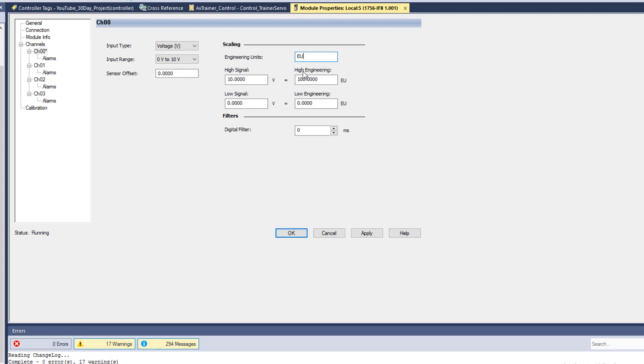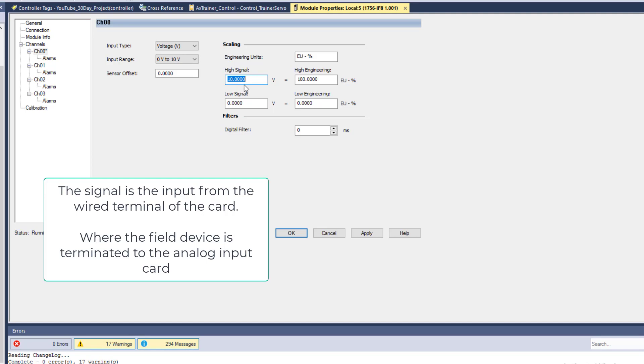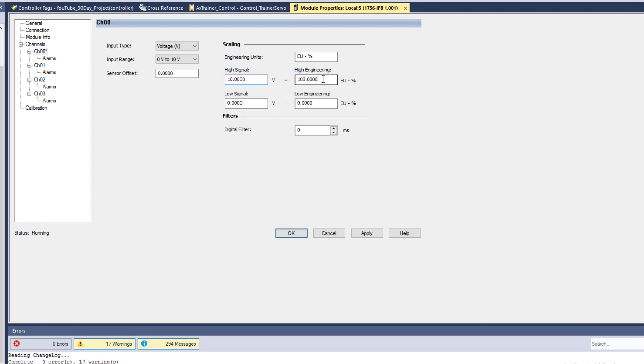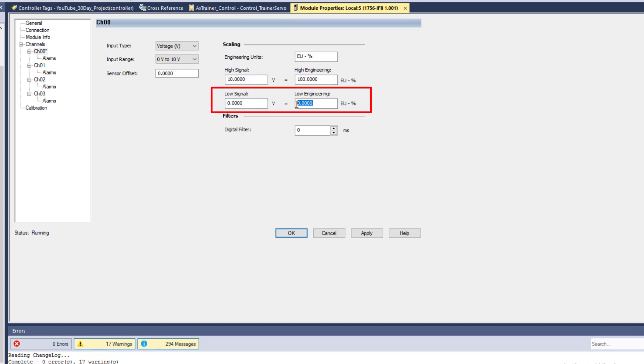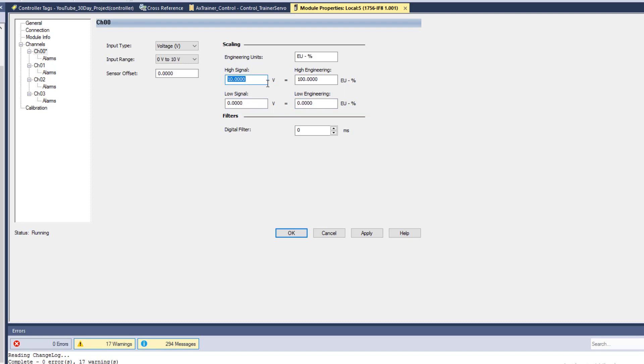In your engineering units — this is just a name field — I'm going to put 'percentage' so you can see that populate. The high signal, which is the high input going to the card from the field device, at 10 volts is going to equal 100. So if I have 10 volts that's 100%, and if I have zero volts that's zero percent. I can change the scaling based upon whatever I want, but in this case I'm using percentages.